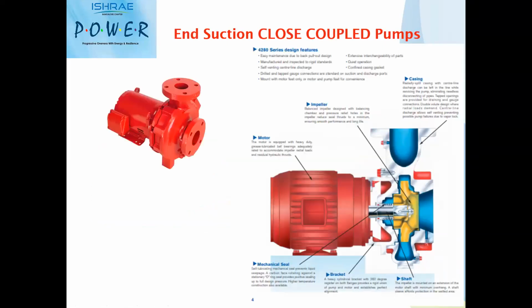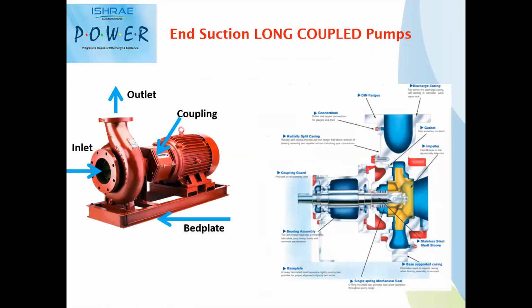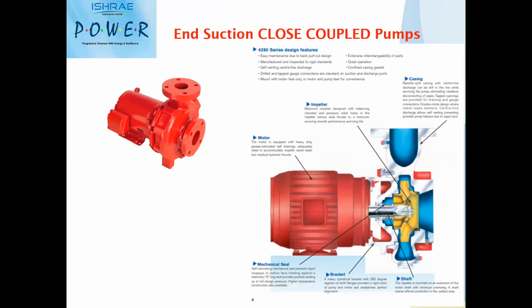When it comes to close coupled pumps, you can see there is no coupling here. Either a stub shaft is directly mounted on the motor shaft, or in some cases the motor has a bigger shaft extension on which the impeller is mounted. Again, this is a typical end suction pump where water enters from one side and goes out the other side. This is close coupled because there is no separate coupling, so the pump impeller is mounted on the motor shaft extension itself. Generally, these end suction long coupled pumps are used for bigger, higher flow rates where you need bigger pump sizes. Close coupled pumps are used for very small circulation pump applications.